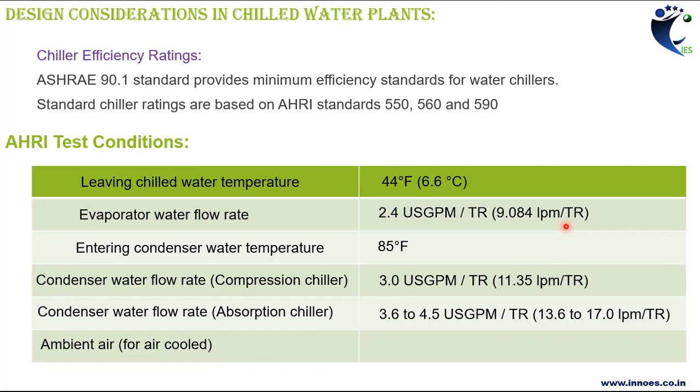Then ambient air for the air cooled chiller, when it is 95 degrees Fahrenheit, that means 35 degrees Celsius, is available. So these are all the test conditions for the AHRI standard.